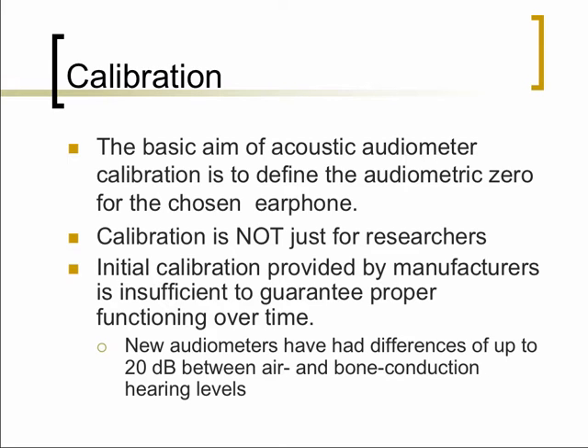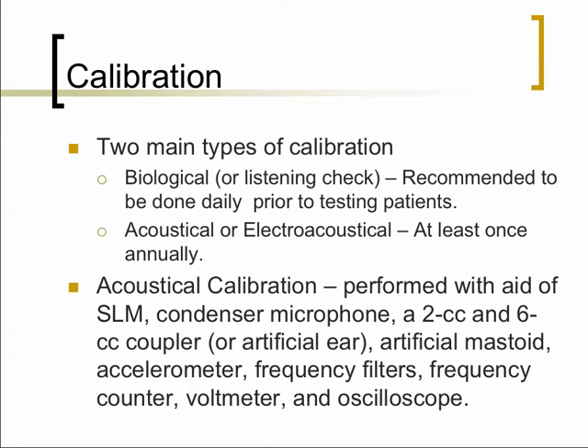In fact, some new audiometers are known to be as much as 20 dB off as soon as you open the box. So what does calibration entail? There are two types of calibration, and the first type of calibration you are probably already involved in. That would be what we call a biological calibration, or simply a listening check.